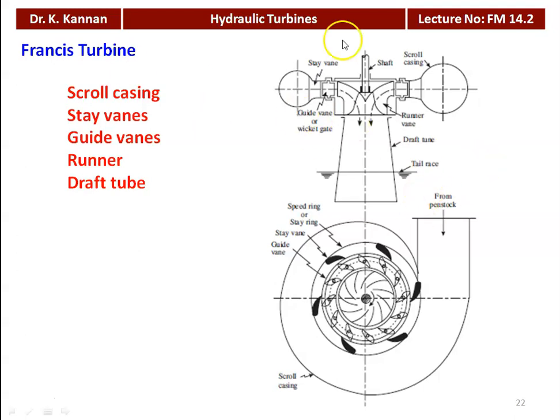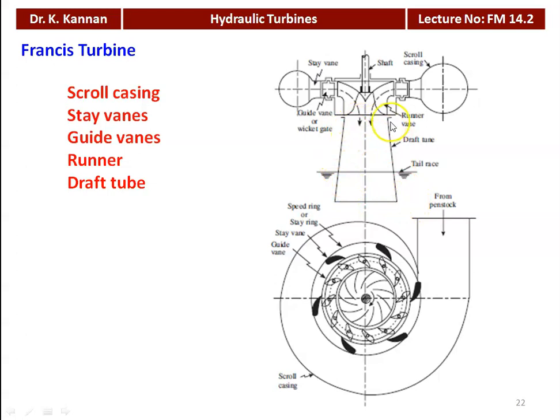The runner blades are made by stainless steel. Then we have the draft tube. After producing power, the water leaves the runner and flows through the draft tube. The cross section of the draft tube is constantly diverging. The water leaves the runner with higher kinetic energy, which is converted into pressure by means of the draft tube. The draft tube has a constantly enlarging cross-sectional area, which converts the velocity of the water into pressure.